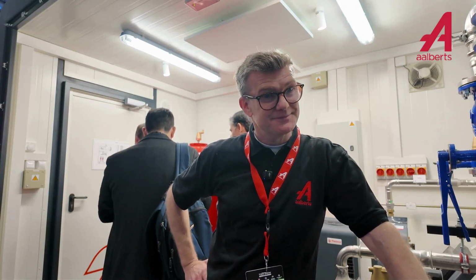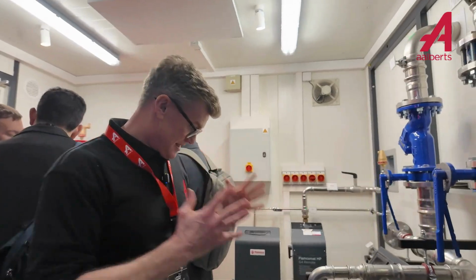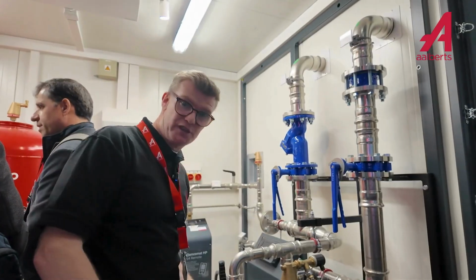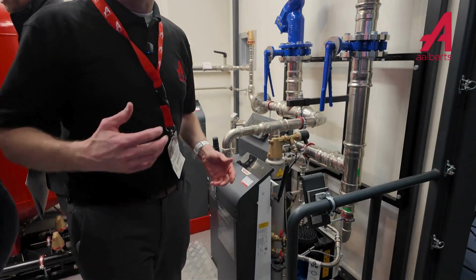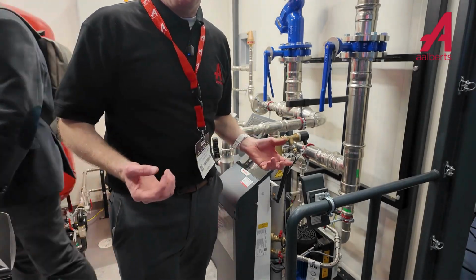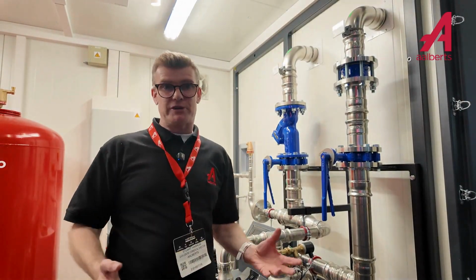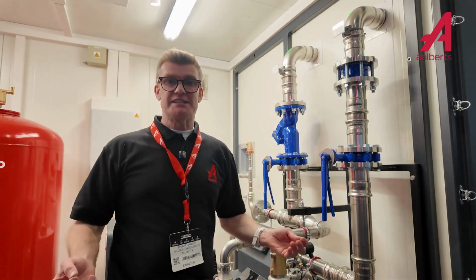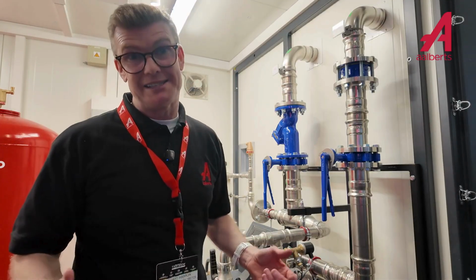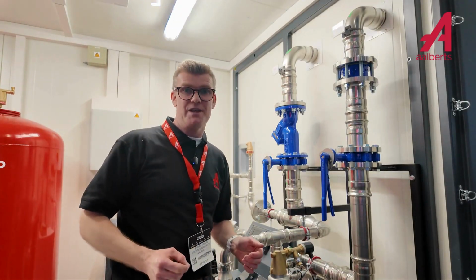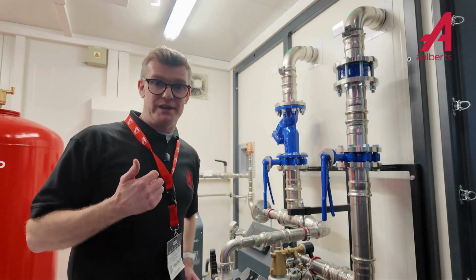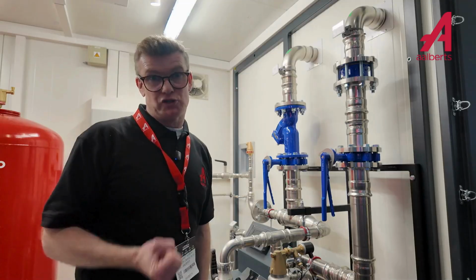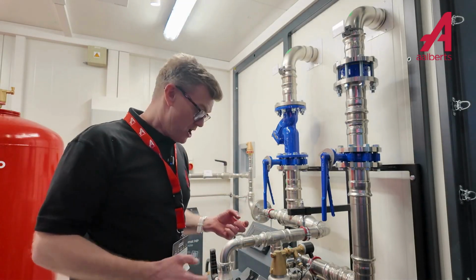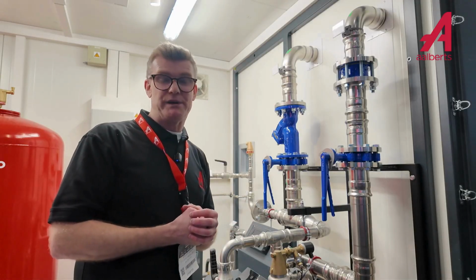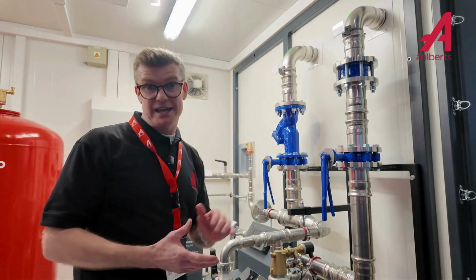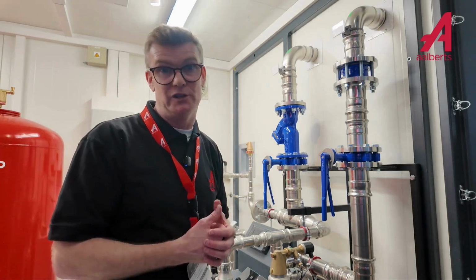I can see people are in there having a look, but can you talk us through what's in this room? This is the vacuum degasser. The main objective of this unit is to eliminate the dissolved gases from your technical cooling circuits. In liquid cooling, in your main primaries, physics dictates that there's a lot of dissolved gases in your lower temperature circuits, so it's vitally important for the integrity and stability of your system to get rid of those dissolved gases. What we do is take a sample from the system, pull a vacuum on it, which expels the dissolved gases out of solution into the atmosphere, and then we re-enter that degassed water back into the cooling system.